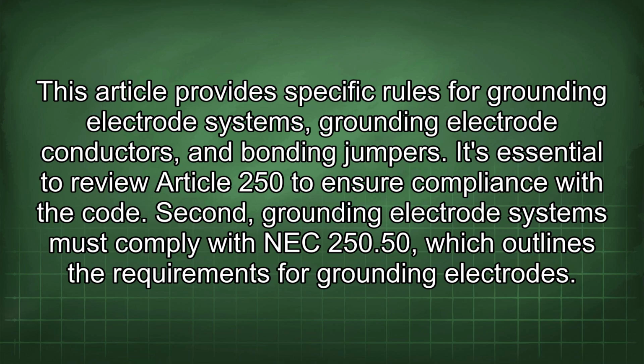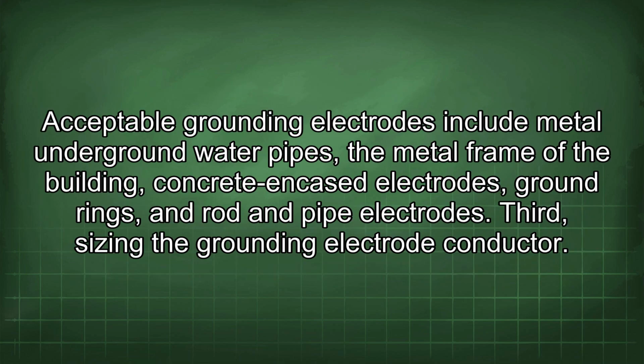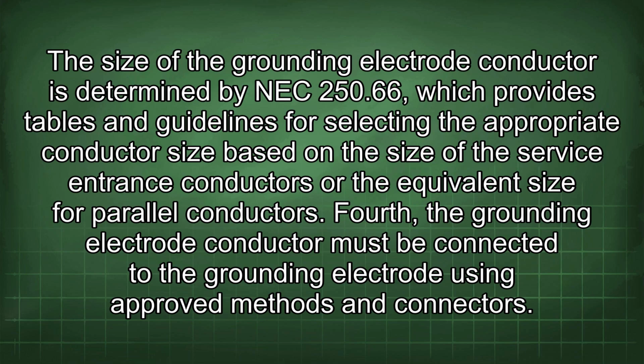Second, grounding electrode systems must comply with NEC 250.50, which outlines the requirements for grounding electrodes. Acceptable grounding electrodes include metal underground water pipes, the metal frame of the building, concrete encased electrodes, ground rings, and rod and pipe electrodes. Third, sizing the grounding electrode conductor. The size of the grounding electrode conductor is determined by NEC 250.66, which provides tables and guidelines for selecting the appropriate conductor size based on the size of the service entrance conductors or the equivalent size for parallel conductors.